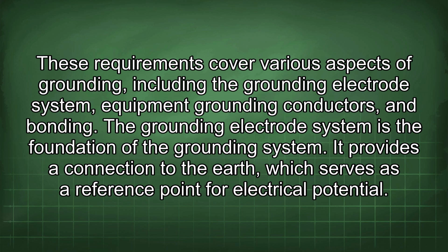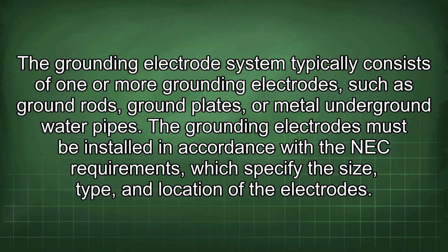The grounding electrode system is the foundation of the grounding system. It provides a connection to the earth, which serves as a reference point for electrical potential. The grounding electrode system typically consists of one or more grounding electrodes, such as ground rods, ground plates, or metal underground water pipes. The grounding electrodes must be installed in accordance with the NEC requirements, which specify the size, type, and location of the electrodes.